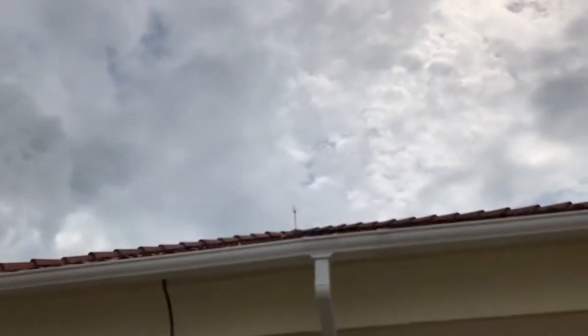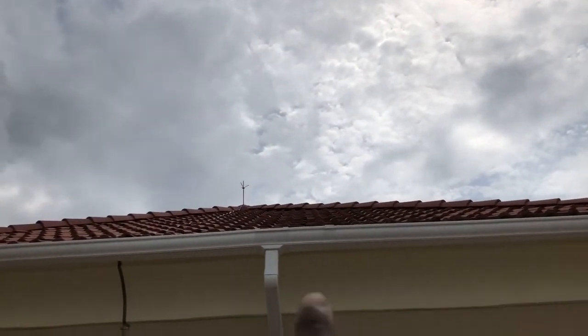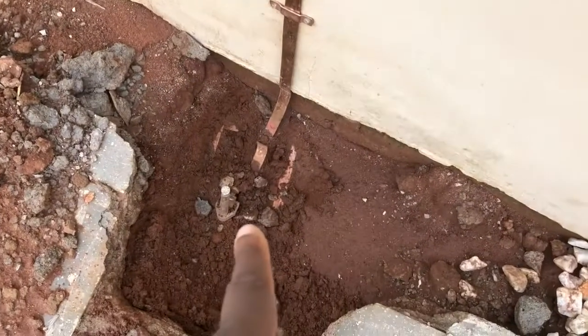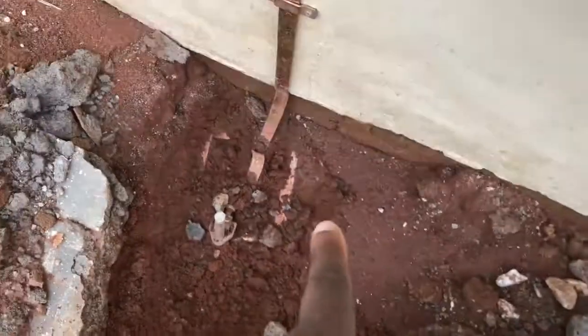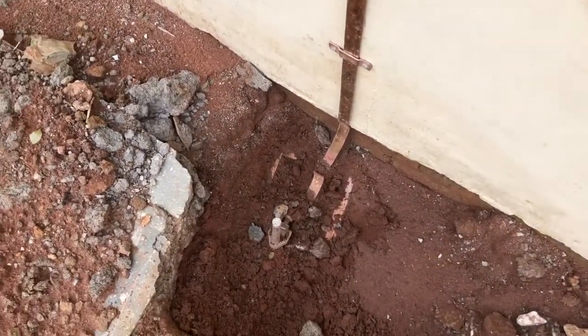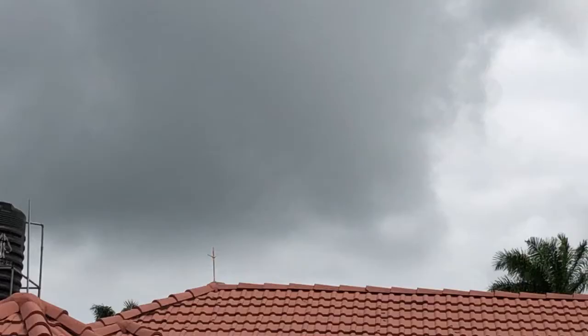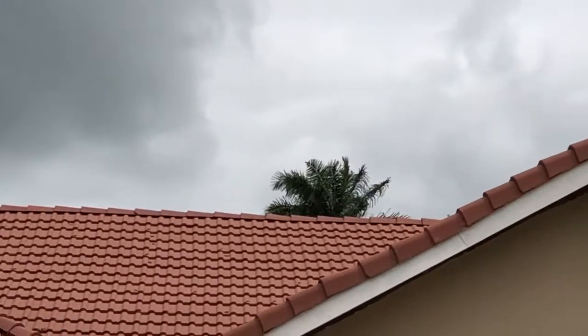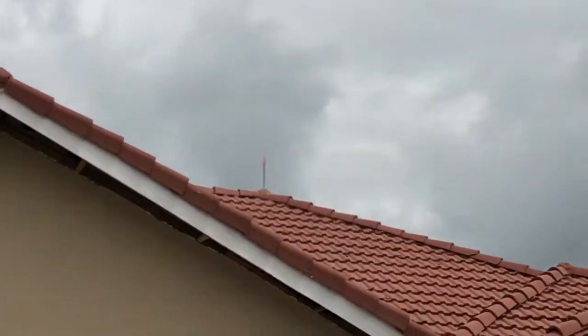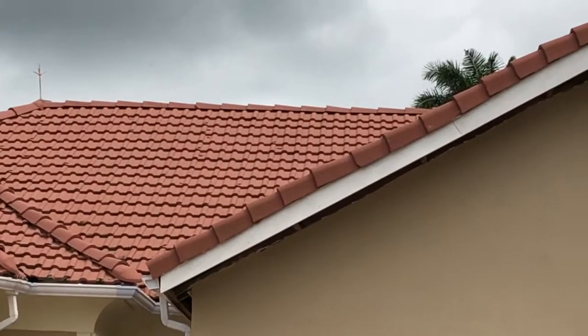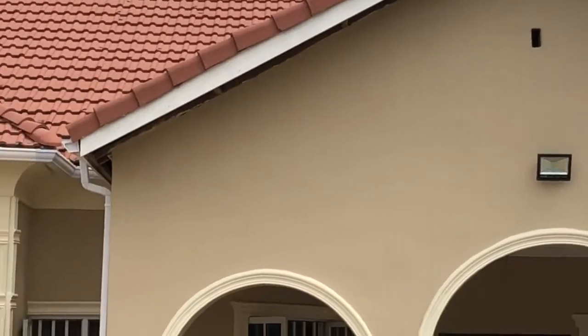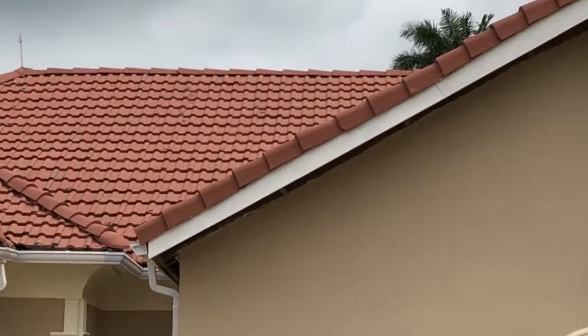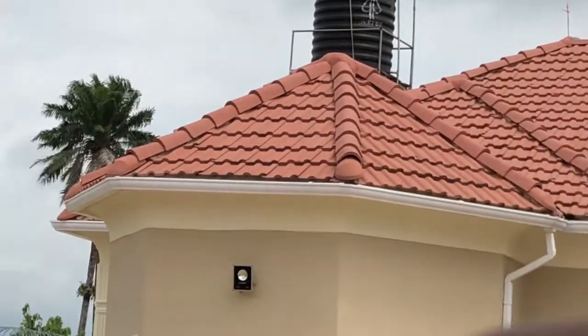Next up is the lightning protection system, which we did 2 lightning electrodes on either side of the roof because of a range of 15 to 20 feet. And you can see the thick copper cabling going straight into the ground, into a mat in the ground. Also, you can see the main ground electrode having been inserted into the ground there. You can see on one side to the other that there are 2 lightning electrodes from side to side to protect the entire premises from lightning strikes, and they are connected by thick copper piping between each other, and that goes all the way into the ground as shown on the side of the house before.